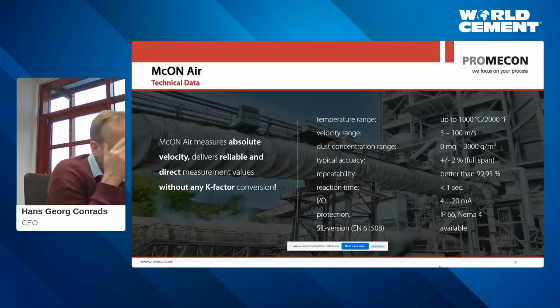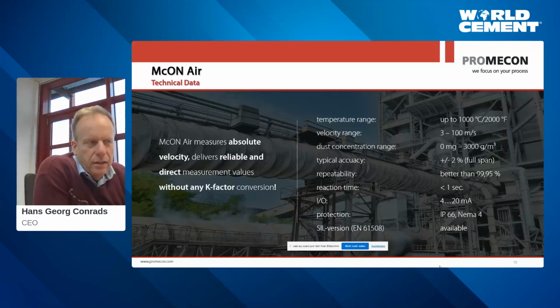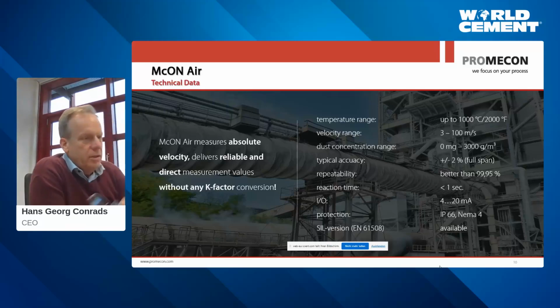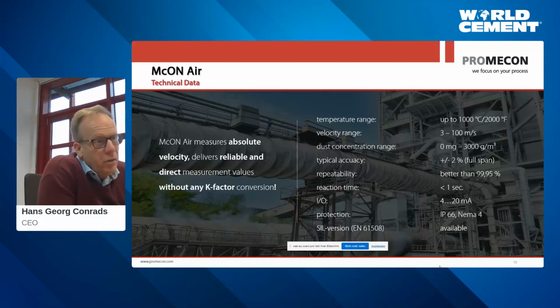Maybe also I should mention here the flow profile, very important. We have two sensors that reach far into the duct. However, the flow profile in your application usually is a very flat profile. Remember, you have 20, 30 meters per second of gas velocity. And at these high gas velocities and these high temperatures, you do not have the typical parabolic laminar flow profile. You usually have a very flat profile, which is just caused by the high level of turbulence of the flow. So the antennas have a very representative measurement accuracy on long straights.